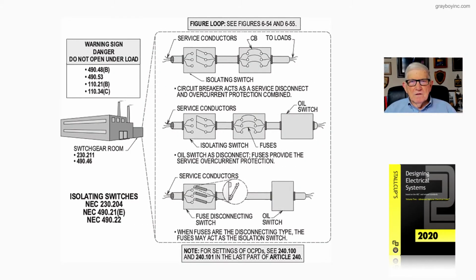Now let's take a look at this figure 17-4 from Stallcup's Electrical Design Book, Volume 2. And we're dealing with isolation switches in accordance with 230.204, 490.21(E), and 490.22. Now notice the basic rule is that an isolation switch has to have a warning label put on it in accordance with 490.22 to identify it as an isolation switch, and do not operate this isolation switch under load.